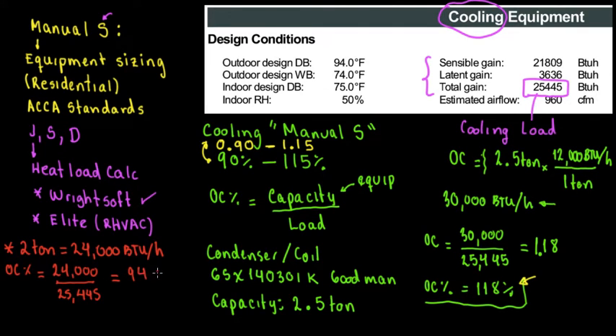Of course times 100. 94% so, technically this is passing. So, this complies with manual S based on ACCA standards. So, now the question to everyone, to the audience is which one would you choose? Option one or option two? Technically would you put in your house a two ton system or a 2.5 ton system?